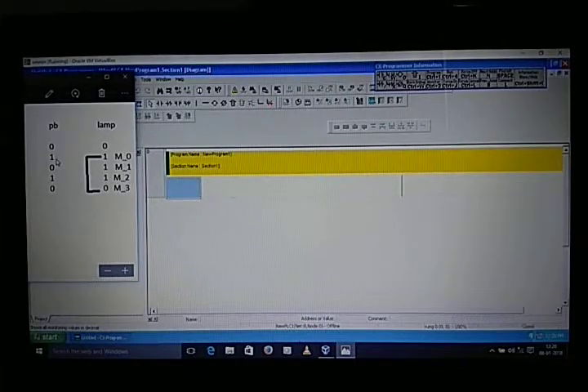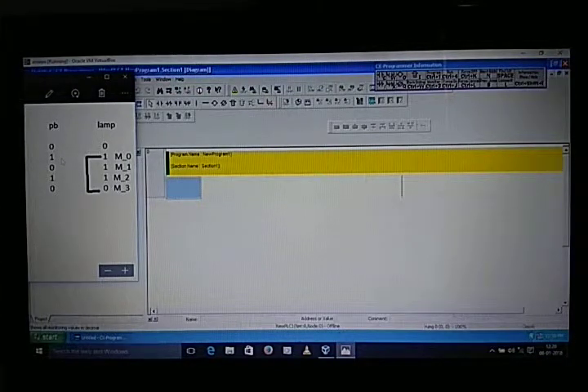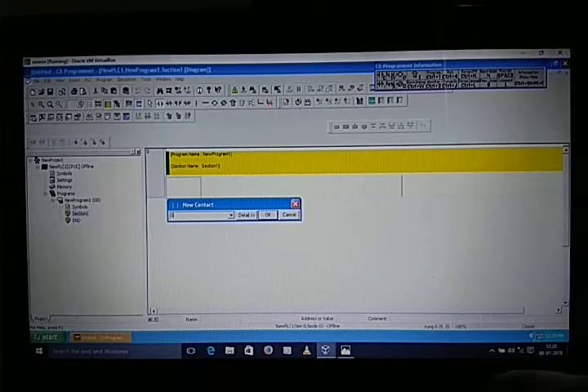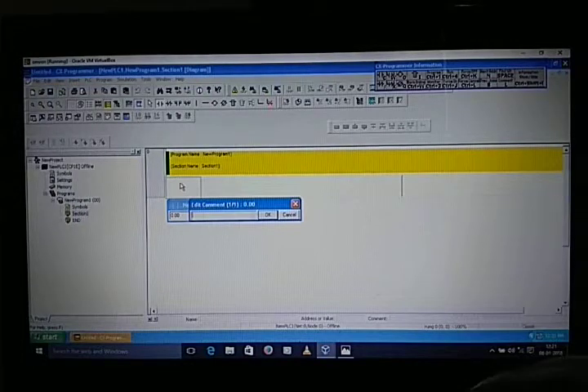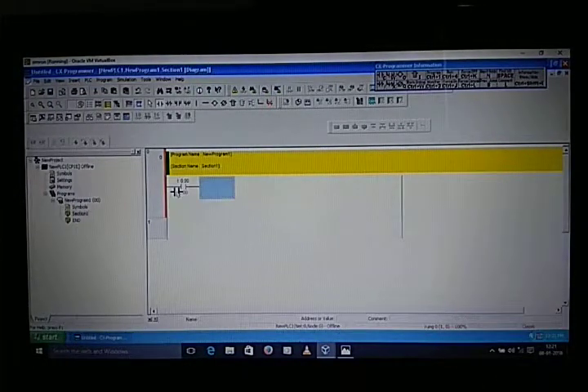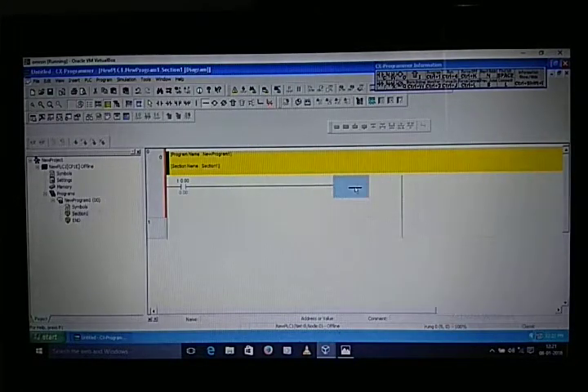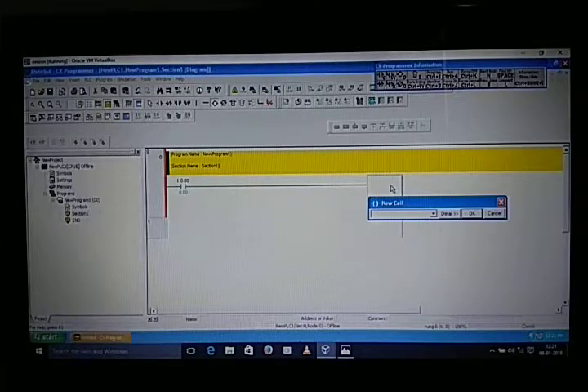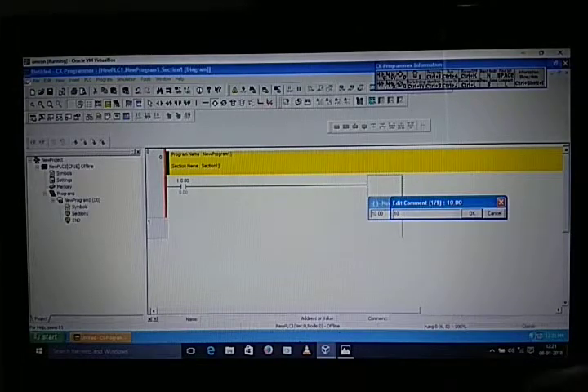Remember: for a one in the truth table, use a Normally Open (NO) contact; for a zero, use a Normally Closed (NC) contact. So here it is one, so we take a NO contact and give it address 0.0. For memory, take address 10.00. I have already given the input and output addressing of Omron.